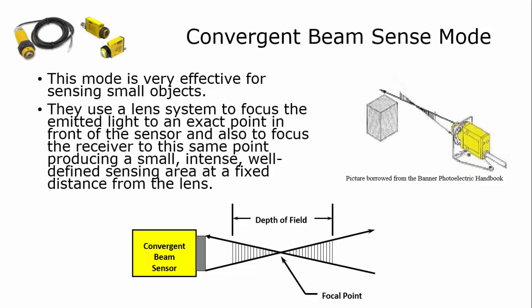The convergent beam sense mode is very effective when you need to sense small objects. They use lenses that focus the emitted light to an exact point in front of the sensor and also focus the receiver to this same point, producing a small, intense, well-defined sense area at a fixed distance from the lens.